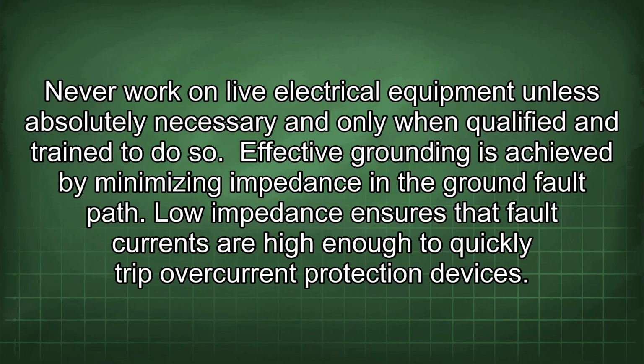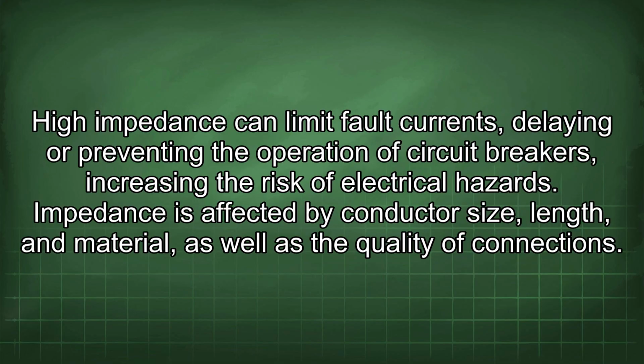Effective grounding is achieved by minimizing impedance in the ground fault path. Low impedance ensures that fault currents are high enough to quickly trip overcurrent protection devices. High impedance can limit fault currents, delaying or preventing the operation of circuit breakers, increasing the risk of electrical hazards. Impedance is affected by conductor size, length, and material, as well as the quality of connections.